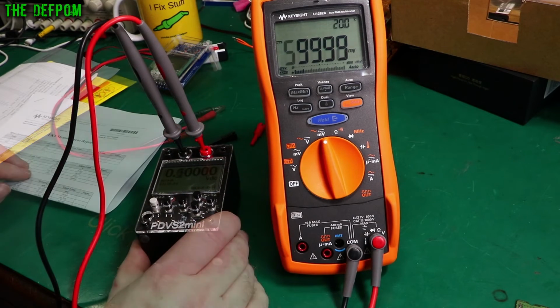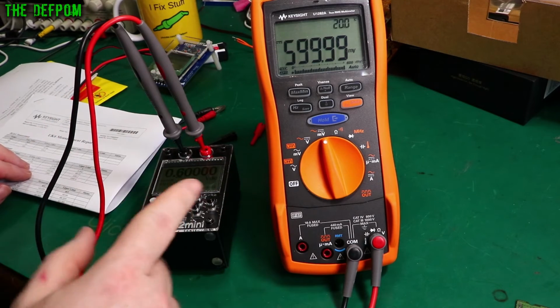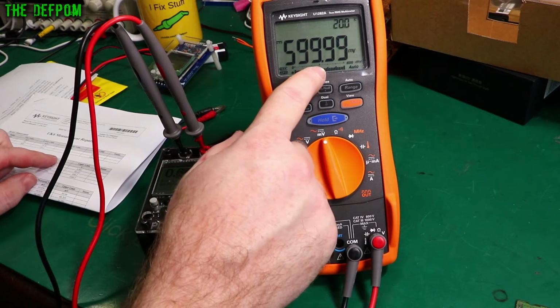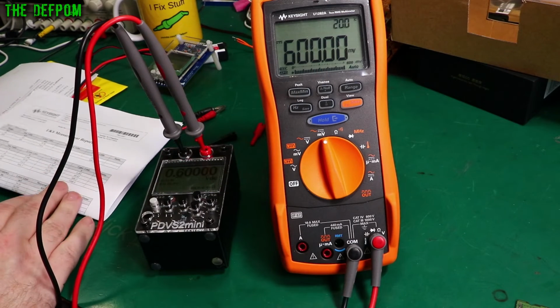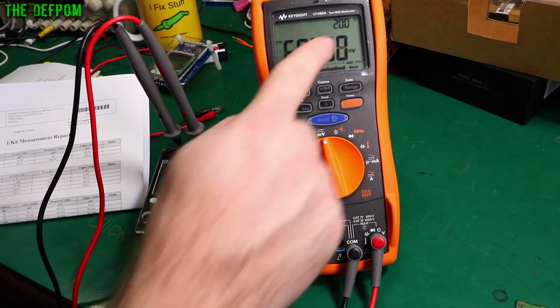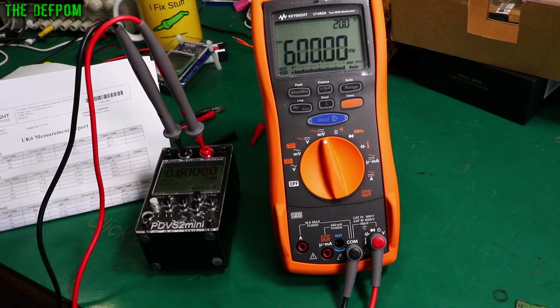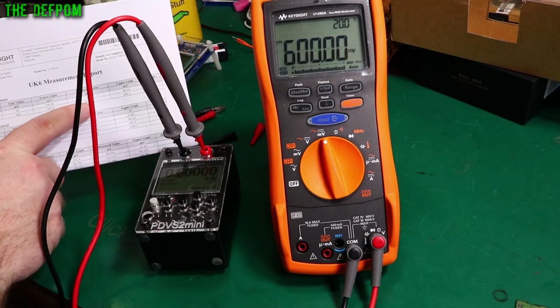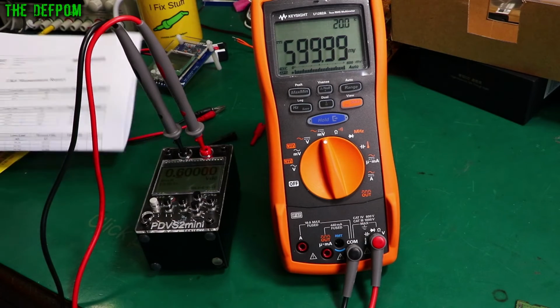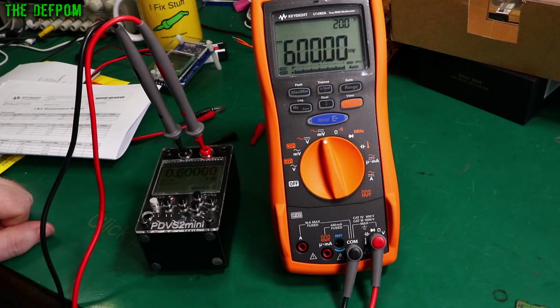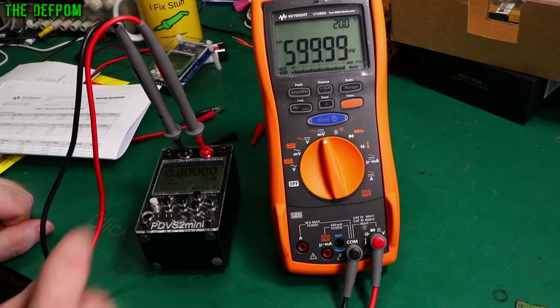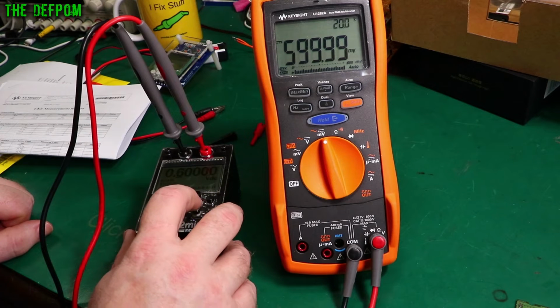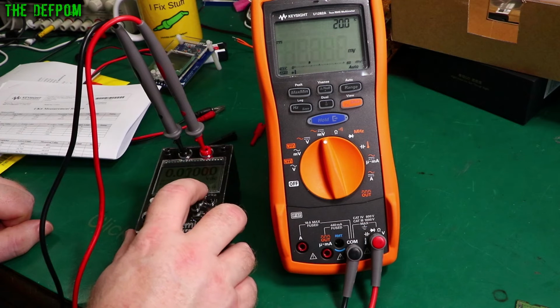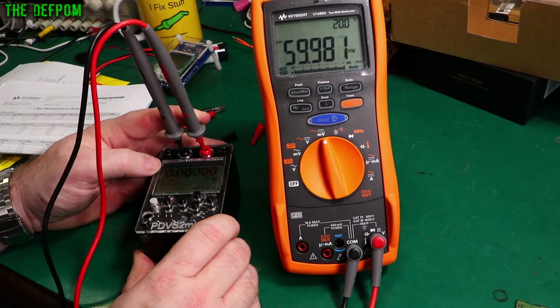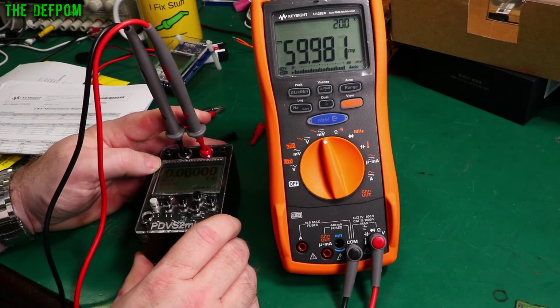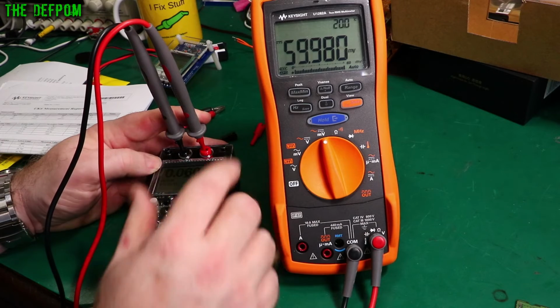In fact, let me check this. Right now I'm generating 600 millivolts and we're getting almost exactly 600 in here. It's got a bit of a rounding thing going on there. Again, my temperature's not perfect. It's not quite the temperature. But on the calibration report it should be 600.01. So it's within 1 count of the calibration, so that's looking good. So if I go down to 60 instead, which is one of the other calibration points, 60 millivolts, the measured value was exactly 60 apparently. We're getting 59.98.